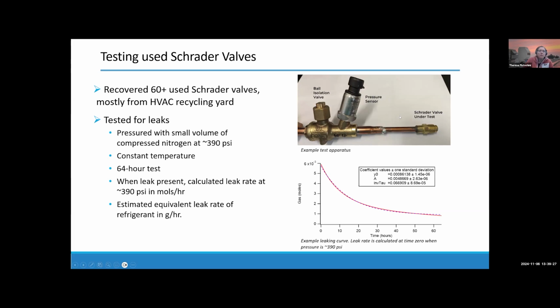Basically, we made this valve body and put pressurized nitrogen in this tube here. Here we're monitoring the pressure in the tube, and then we put the Schrader valve on. If the valve is not leaking, you would expect the pressure to remain constant over time. But if the valve is leaking, you lose nitrogen and your pressure decreases. This is a very small volume of nitrogen so that we can detect the leak fairly quickly. Here's an example on the bottom corner of a leaking valve, and you can see how we lose nitrogen over a couple of days. We then calculate our leak rates of the nitrogen, and although it's not perfect, it's a bit of an approximation, we estimate what that would mean in terms of lost refrigerant gas.